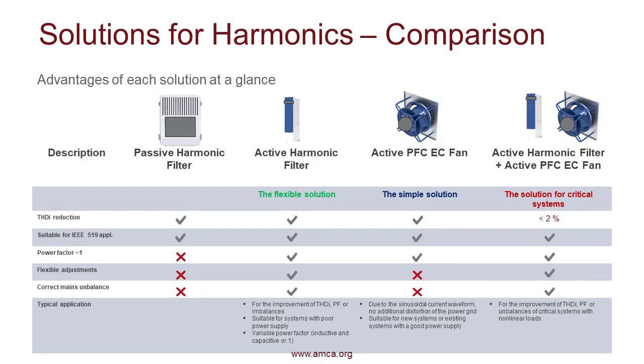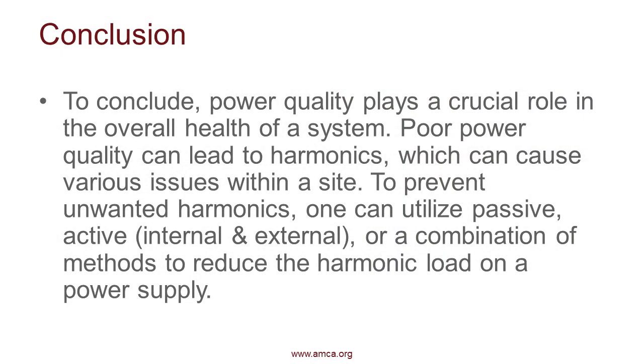So here we can see that the total harmonic distortion can be reduced to less than 2% in laboratory conditions. We can see that it's suitable for IEEE 519. We know that the power factor is increasing. It's a flexible adjustment solution because that active harmonic filter can be calibrated to your system, and it's correcting your mains unbalance.